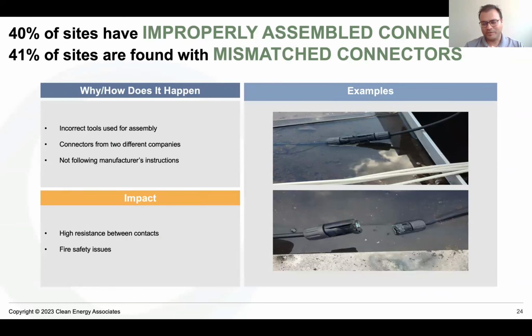Cross mating is an important word. We are seeing issues regarding connectors like improper assembly, broken connectors, and cross-mated or mismatched connectors. Mismatched connectors refers to a situation where you have the positive and negative side of the connector from two different manufacturers. This is a big no-no.